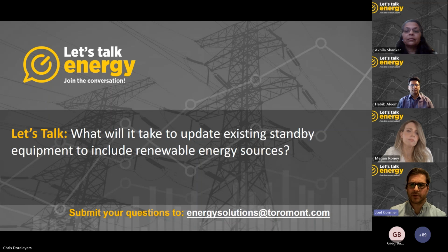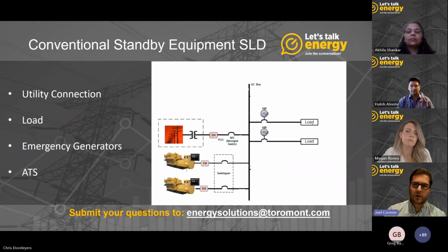So if we can jump to the next slide, please. So first off, we would require a single line diagram of the existing electrical infrastructure along with information, model numbers, all that type of stuff for the existing assets on site. So here on the screen, we can see an example of a typical or conventional single line diagram, which includes standby equipment. As you can see, we have a utility connection, we have our load, we have emergency gen sets, and in most cases, we will also have automatic transfer switches to detect that loss of utility power and then send the start commands to the standby assets.